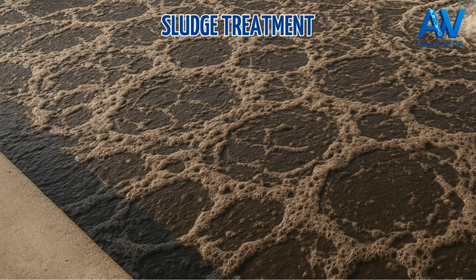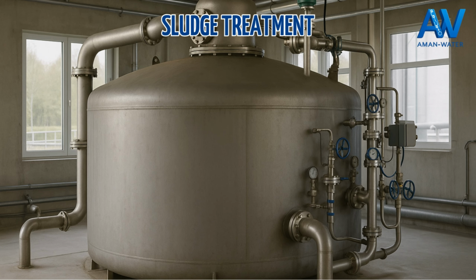Next comes stabilization. The objective is to reduce the biological activity responsible for odors and fermentation. Two main processes exist. The first is aerobic stabilization. Air is supplied, microorganisms rapidly consume the material and produce heat. The second is anaerobic stabilization. This process takes place in the absence of oxygen, inside closed digesters. The degradation is slower, but it produces biogas, a mixture rich in methane.